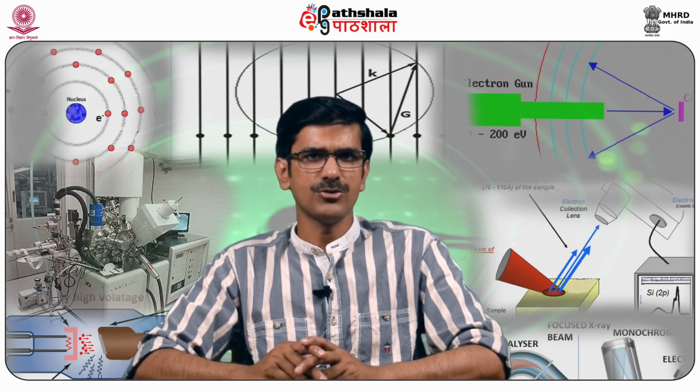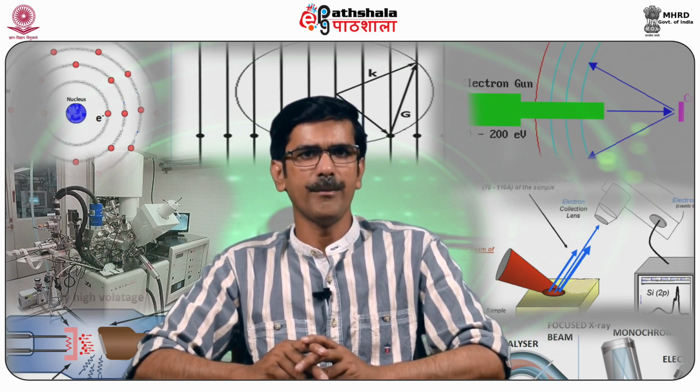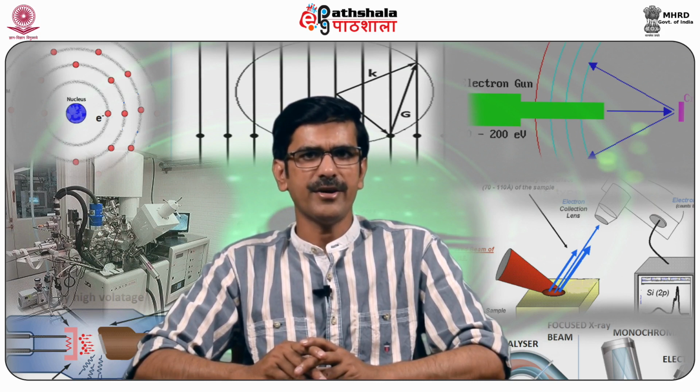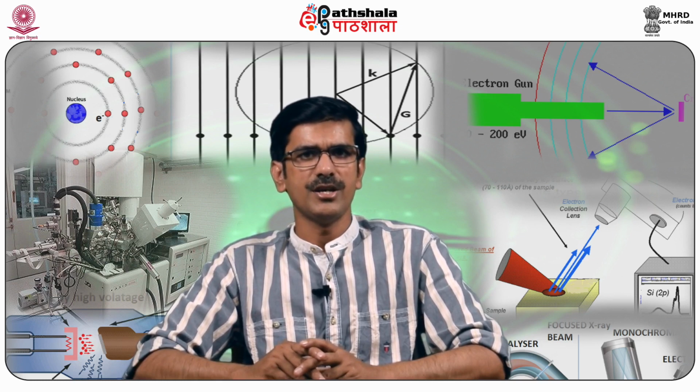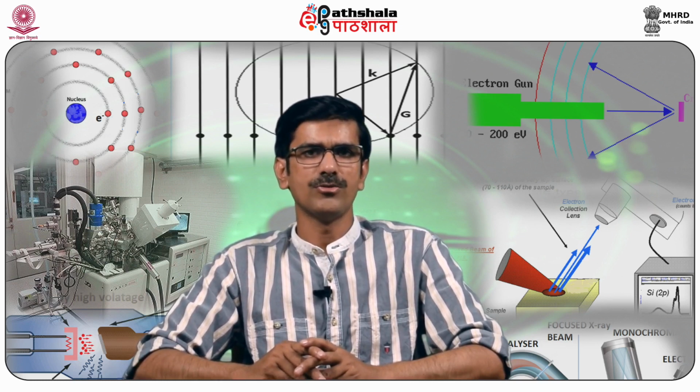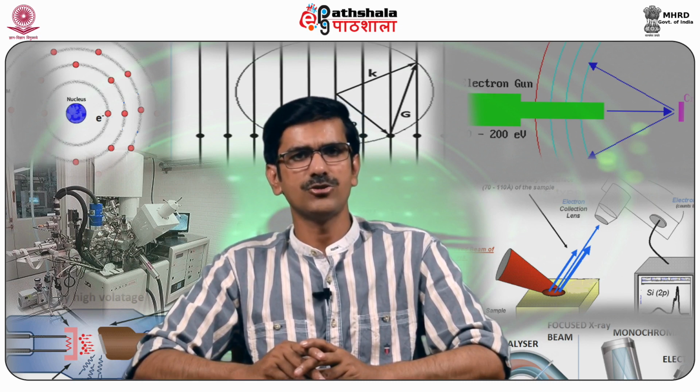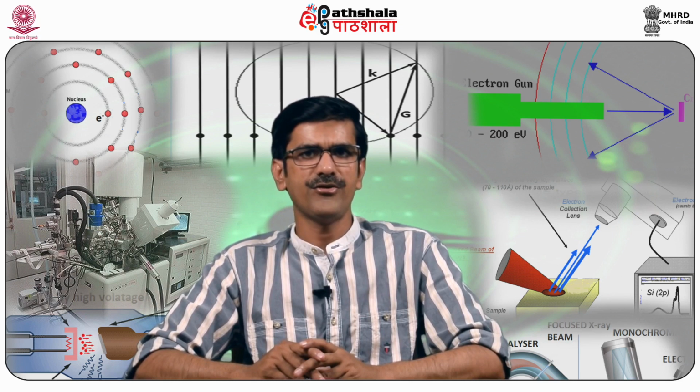This is accomplished to a large extent by the differential pumping that is afforded by the entrance slit. The gas to be studied is leaked into the source volume. For a typical slit size of 1 cm by 0.2 mm, a differential pressure of 10⁻³ can be maintained if the spectrometer is being pumped at the speed of 100 liters per second.